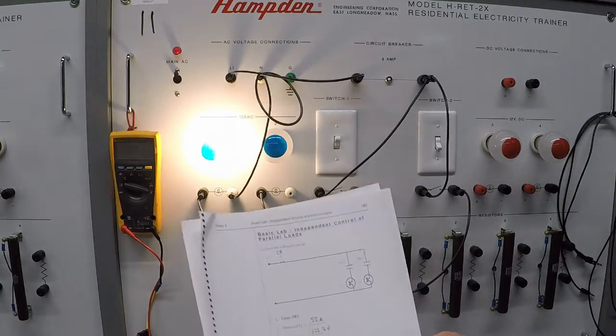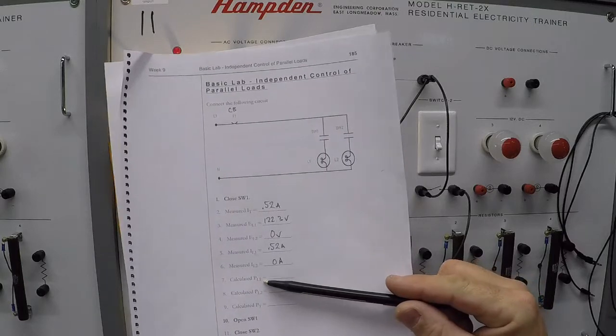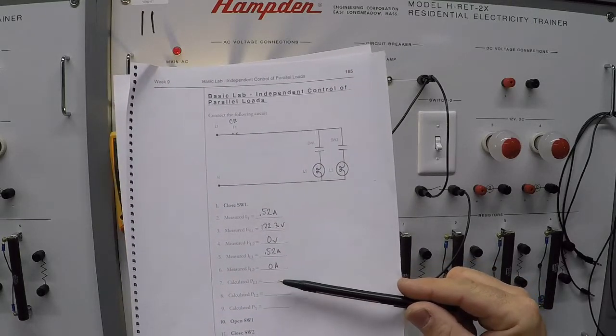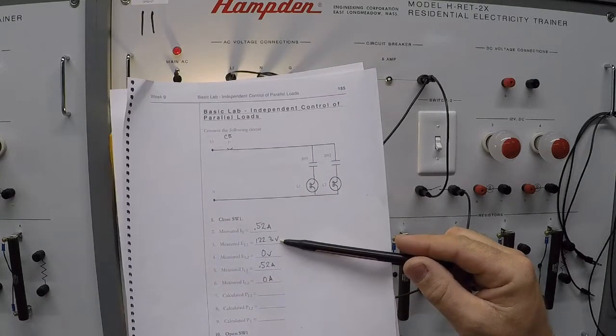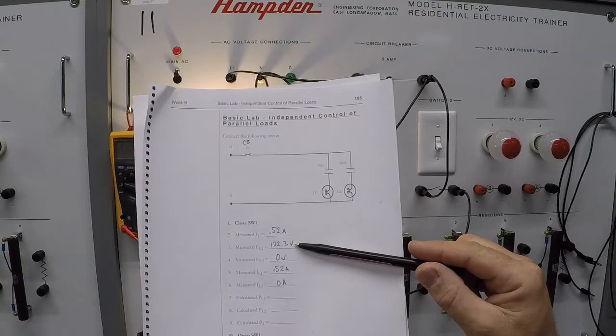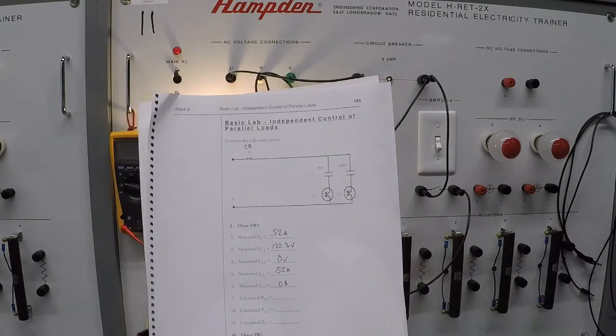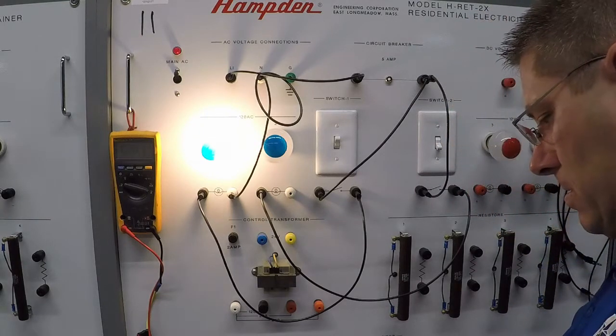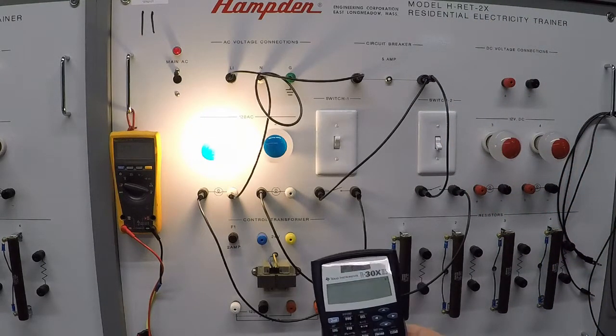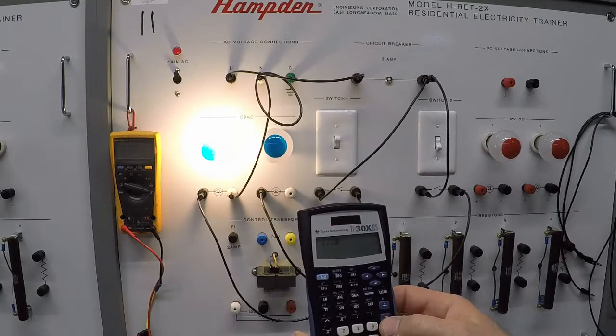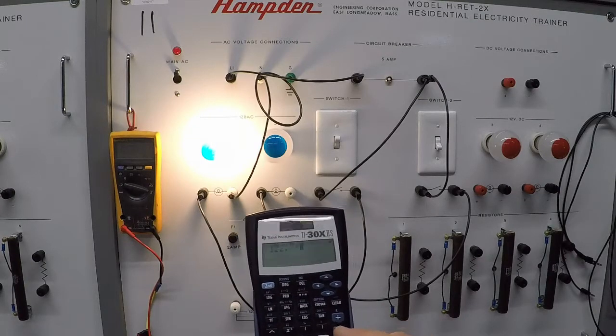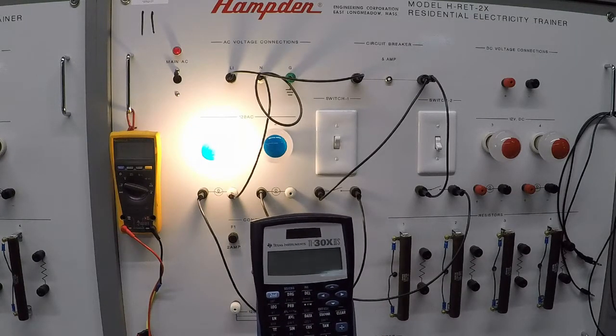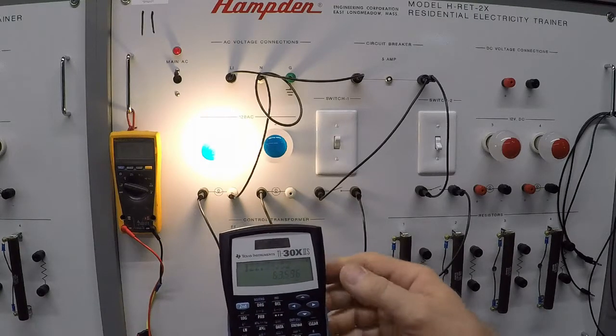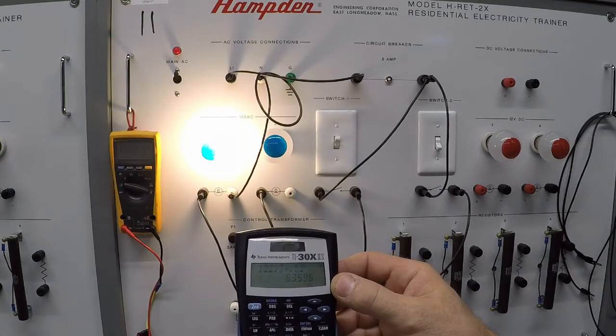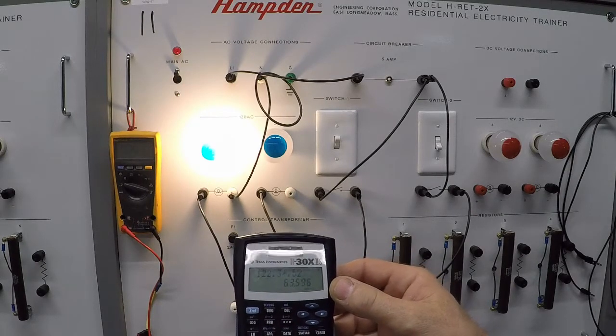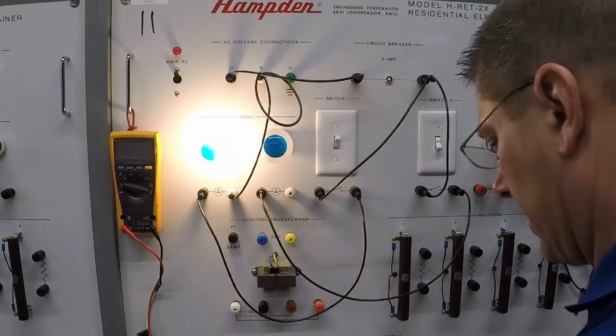In step 7, we're going to calculate our power for L1. So that requires us to take our voltage measurement, 122.3 in this example, times 0.52 amps. 122.3 times 0.52, and that gives us 63.59 watts, or 63.6 watts, rounding up.